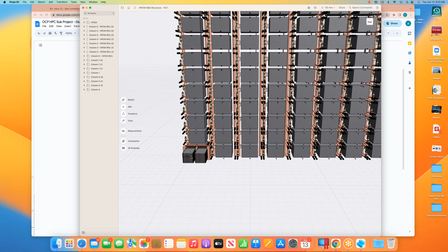One thing John Summers brought up at RISE in our discussion was that if you're returning 65 degrees C hot water, eventually, no matter how much insulation you have, the room itself will rise to 65 C if you don't do some level of cooling of the room. That's one thing I haven't really emphasized here, but it's something we need to think about. I was of the mind that we would try to insulate these modules and the main processor.